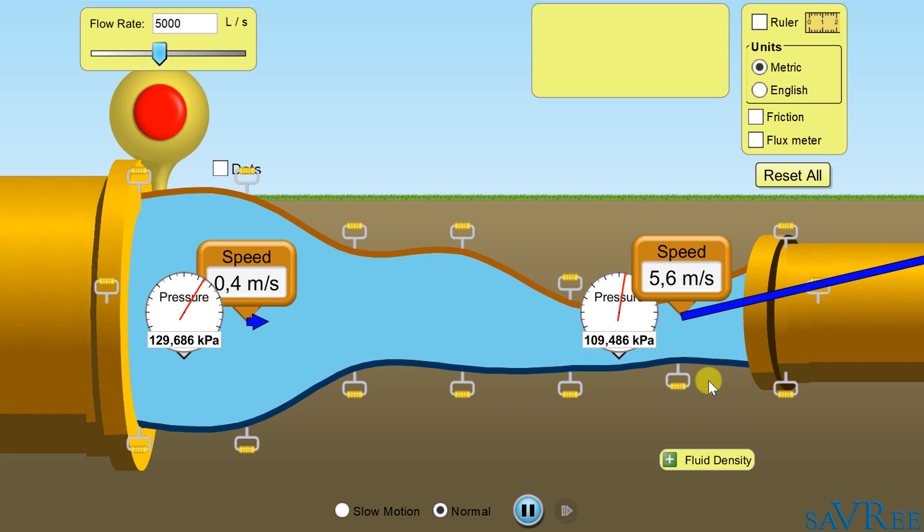So a quick recap. If the flow path becomes larger, the speed reduces and the pressure increases. If the flow path becomes smaller, the speed increases and the pressure reduces. And you can see we've got quite a lot of pressure reduction when we compare both the left and the right. So let's now go back to our impeller and apply Bernoulli's principle in order to figure out how it works.